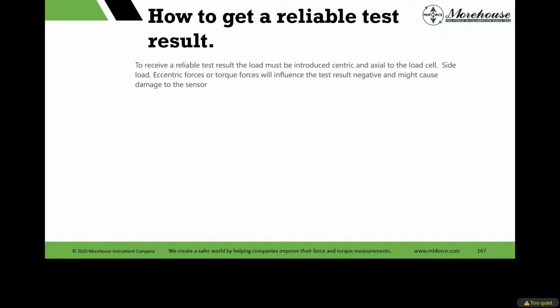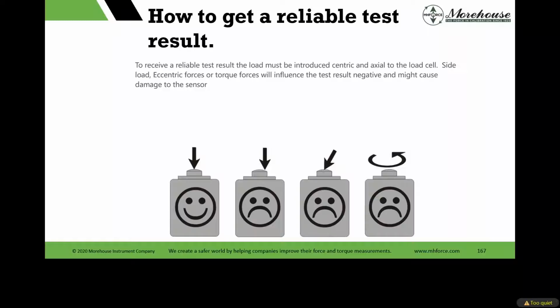There are things you want to make sure you're keeping minimized. You want to keep the load centric, which is our little happy face over there, and you want to avoid side load, eccentric forces, or torque forces. And torque forces especially can cause damage to the sensor depending on how it's made. So really we want our happy face over here, and we want to facilitate that with adapters. We've had some, like button load cells and the others.